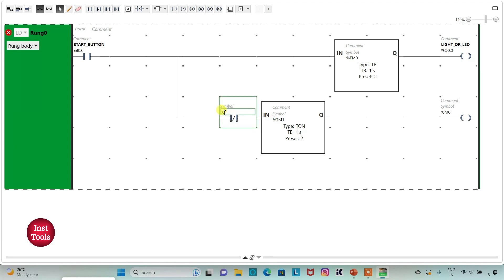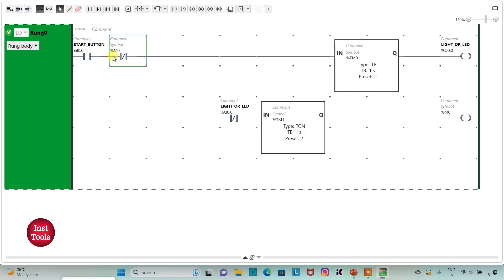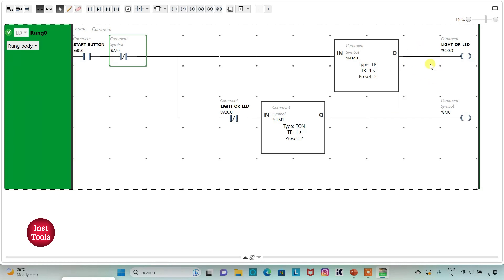I will insert a normally closed contact and assign it the same address as the light or LED, which is Q0.0. Then I will insert one more normally closed contact and assign it the address of the memory bit, M0.0. When I turn on the start button, the current will flow through it and through the memory bit, and the LED will be on for 2 seconds, after which it will be turned off.